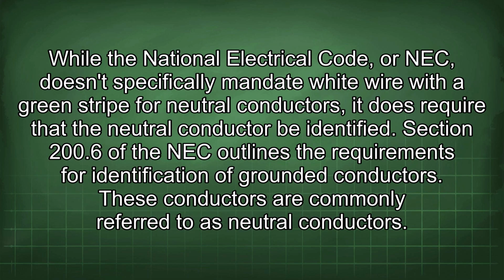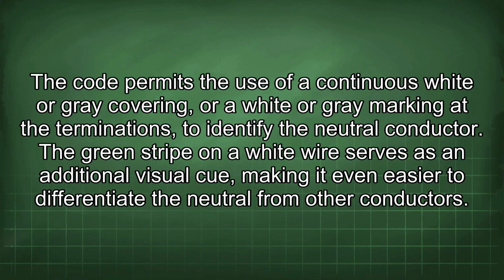While the National Electrical Code, or NEC, doesn't specifically mandate white wire with a green stripe for neutral conductors, it does require that the neutral conductor be identified. Section 200.6 of the NEC outlines the requirements for identification of grounded conductors. These conductors are commonly referred to as neutral conductors. The code permits the use of a continuous white or grey covering, or a white or grey marking at the terminations to identify the neutral conductor.